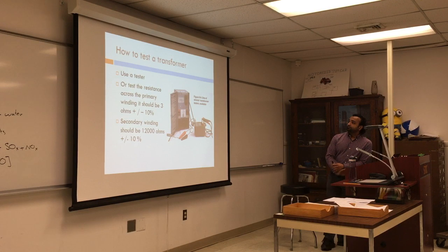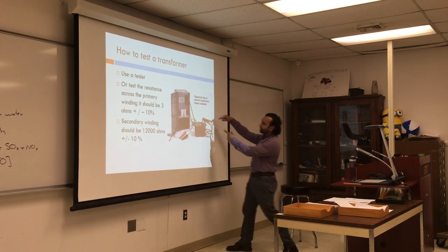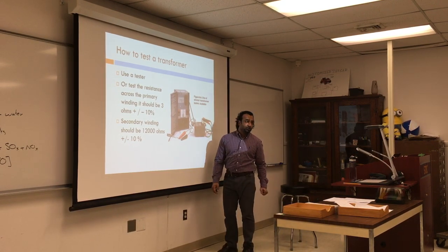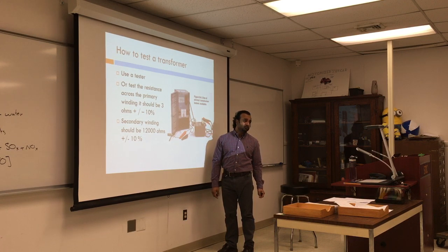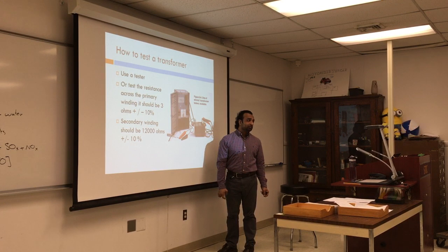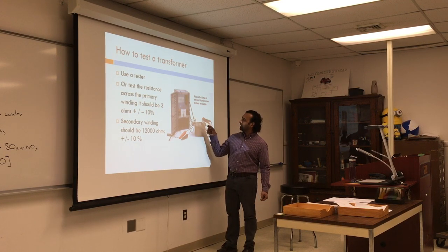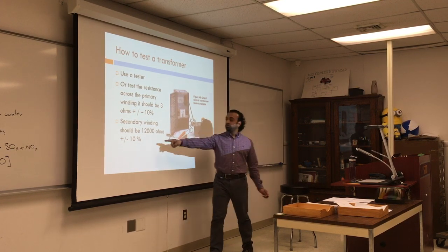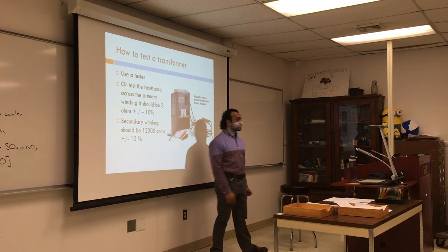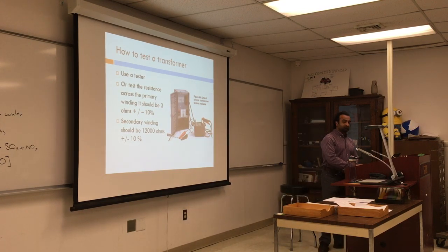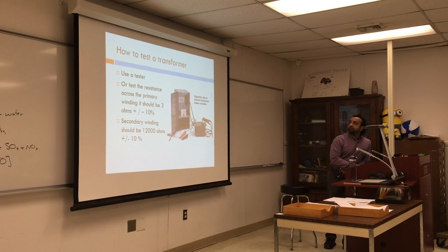You can test the resistance across the secondary winding, which is here. And when you do that, make sure it's unplugged. You test the resistance when things are off, so don't do that unless you take it out. Test the resistance. It should be around 12,000 ohms, plus or minus 10%. That's a good way to test a transformer.